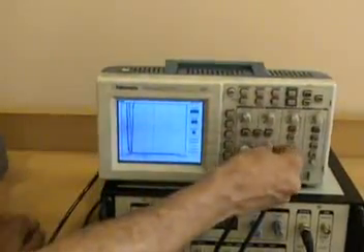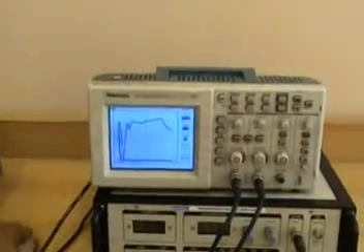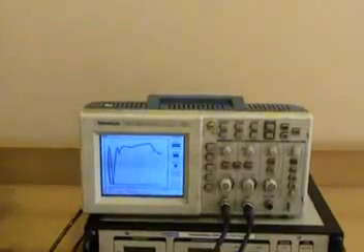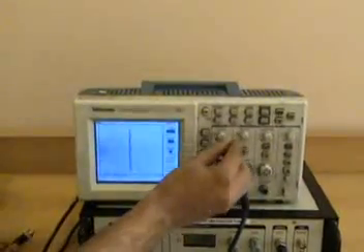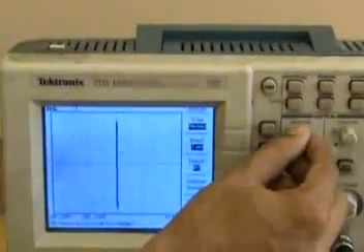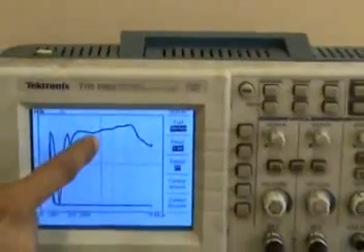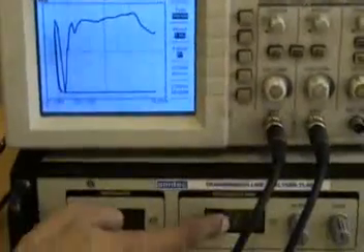If your display doesn't come, then you have to select the attenuators of voltage at X or Y. Now here it is less, you have to select it accordingly so that the display almost comes in the center. Now to ensure that we are measuring the center frequency, because whatever is displayed here is actually the center frequency, if I remove the Y cable, I can see now this has to be precisely put to the center. Now this is actually 136 megahertz which is being displayed here.